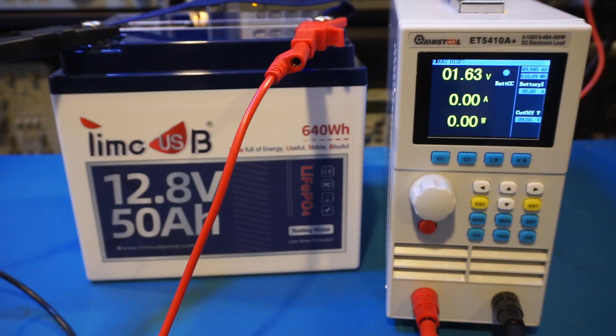Okay, let me charge up the battery again and we'll do some load testing. According to the manual, the battery can sustain 50 amps discharging current continuously, so let me verify that. I've connected an inverter to the battery, using a variac to control the output so I can adjust the load more precisely. The load is an electric heater. I have a clamp meter measuring the battery output current and a multimeter to monitor the terminal voltage. Let me zero out the reading here.